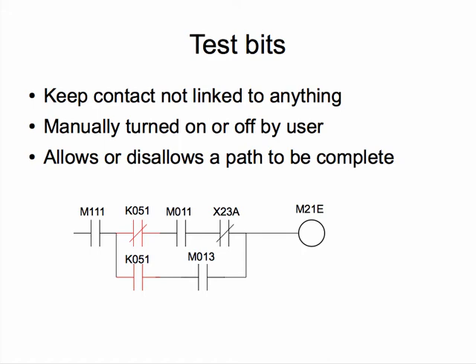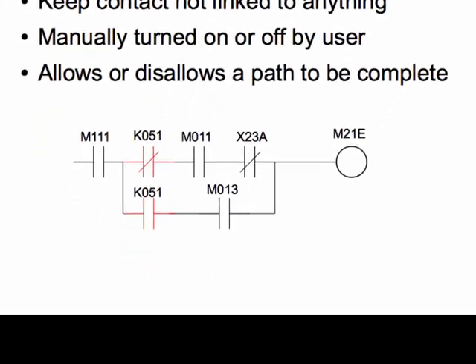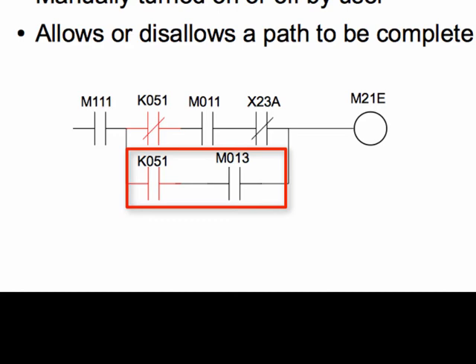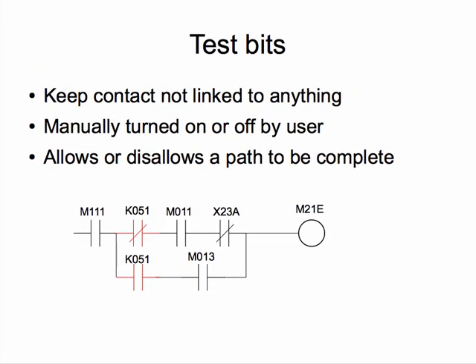Lastly, let's talk about test bits. They are basically keep contacts inside the program controlled by the user — turned on or off manually. They stay that way even when the control panel is restarted because they are keep contacts. Using the same example, I could only allow one of the logic conditions to possibly be completed. Here, we added K051 as the test bit. As long as we keep it off, only the upper logic can be met. When we turn the test bit on, only the lower logic can be met. This is very useful when adding new lines of code. All the new code can be kept behind a test bit. We can turn the test bit on to trial the new lines of code, and if there is any issue, we can just turn it off. In the manufacturing world, this is critical in order to avoid production downtime.